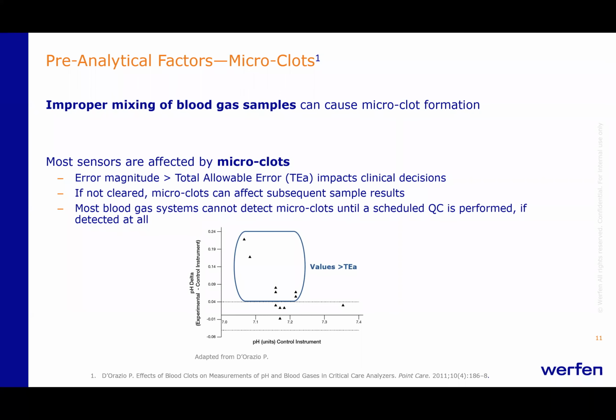In 2011, Dr. Paul D'Orazio and his associates published a paper on the effect of microclots. Improper mixing of blood gas samples can cause microclot formation. And here are some of the conclusions from that study. Most sensors are affected by microclots. The error magnitude exceeds TEA, which is total allowable error, and can impact clinical decisions. If not cleared, microclots can affect subsequent sample results. Let me say that again: if not cleared, microclots can affect subsequent sample results.